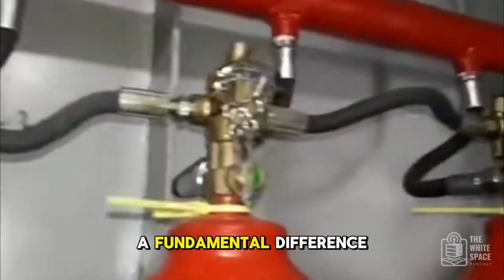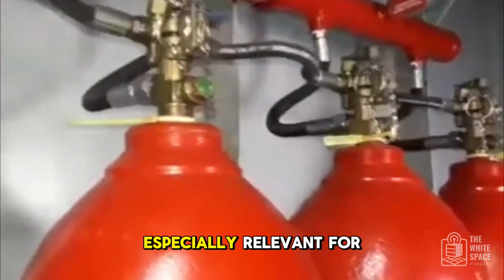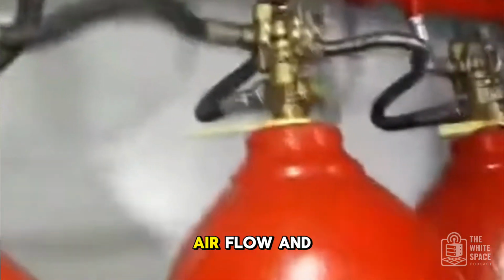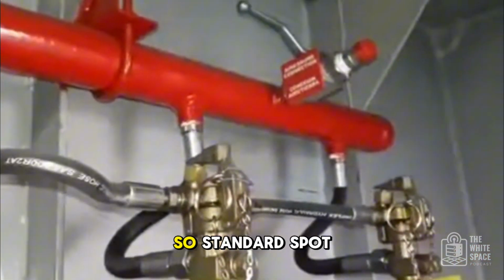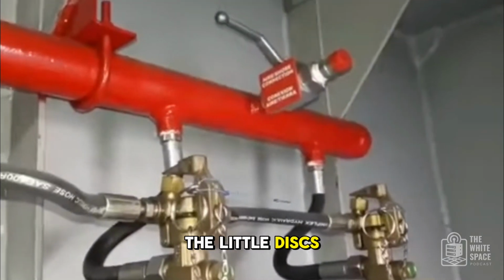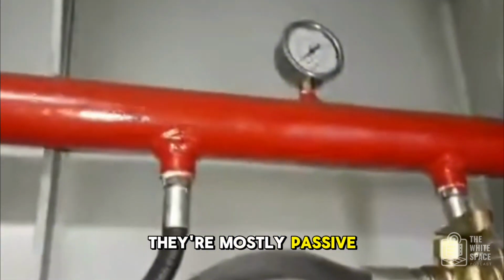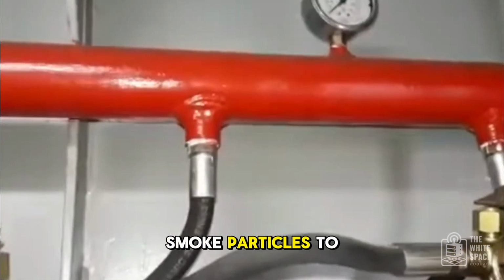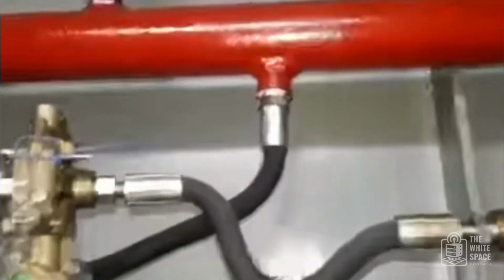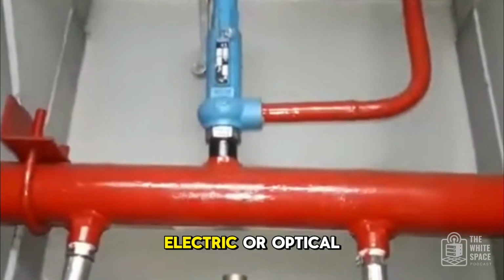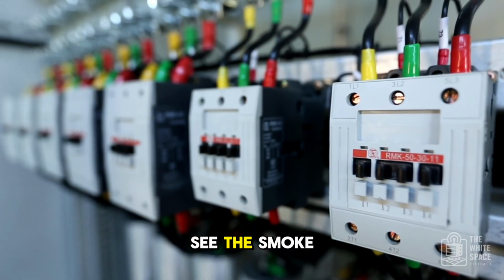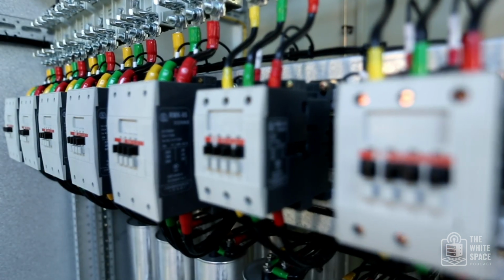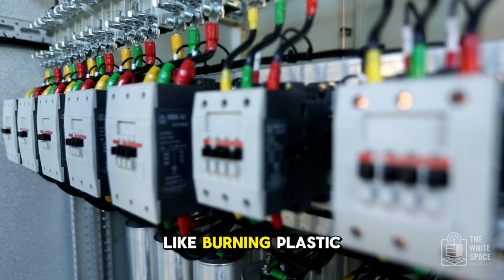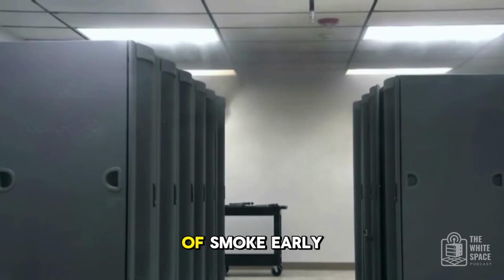Great question. It's a fundamental difference in how they work, especially relevant for data centers with their high airflow and sensitive gear. So standard spot detectors, the little discs on the ceiling, they're mostly passive. Okay. They wait for smoke particles to drift into their detection chamber. There are a few main types, photoelectric or optical ones. See the smoke particles scattering a light beam. They're good for smoldering fires like burning plastic or wiring that make a lot of smoke early on.